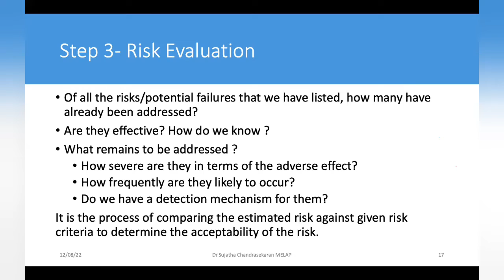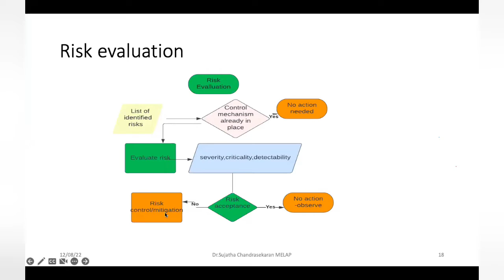So how do we do this? This is the list of identified risks. If a control mechanism is already in place and you think it is effective, no action is needed. But if there is no control mechanism, you evaluate it based upon the severity, criticality, and the detectability, and look at the risk now. If it is an acceptable risk, it's very rare, it's not severe, and the detectability is good. If it happens, I would immediately pick it up. Then you don't need to take any action, you can observe. But if it is not so, then the risk control or mitigation is required.